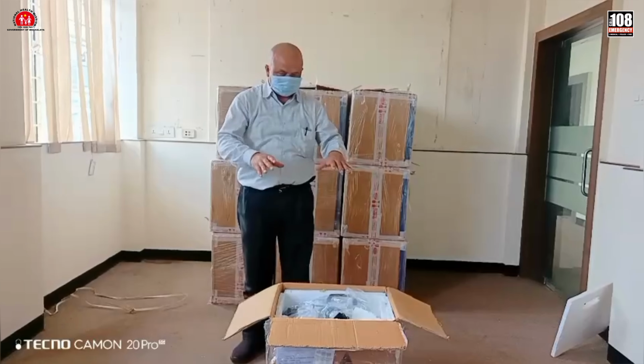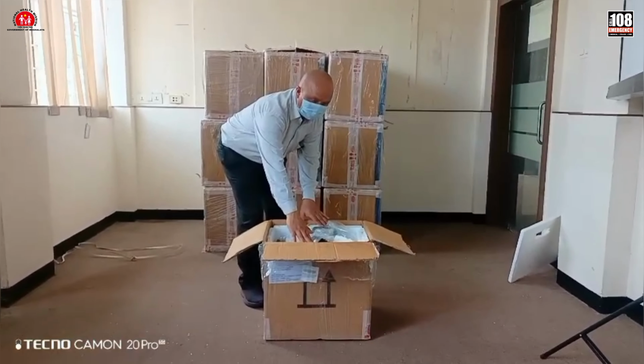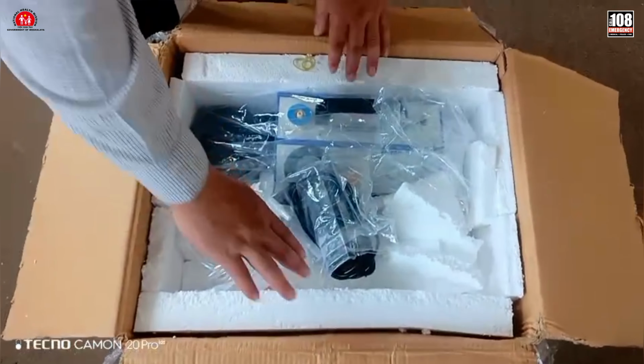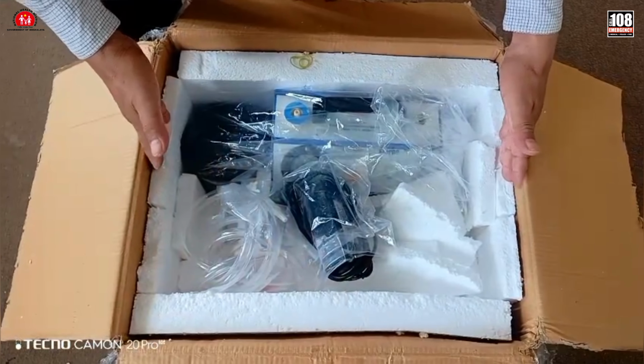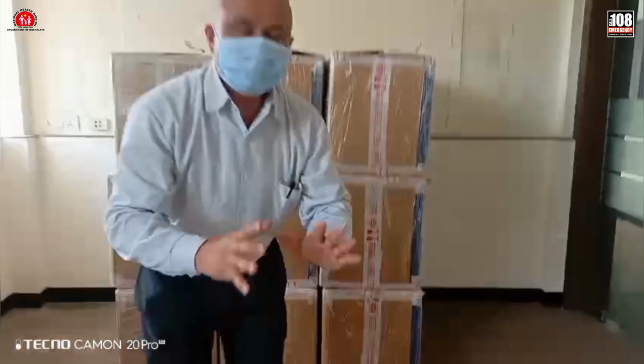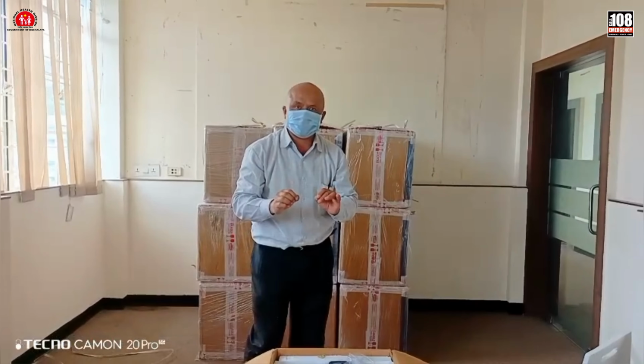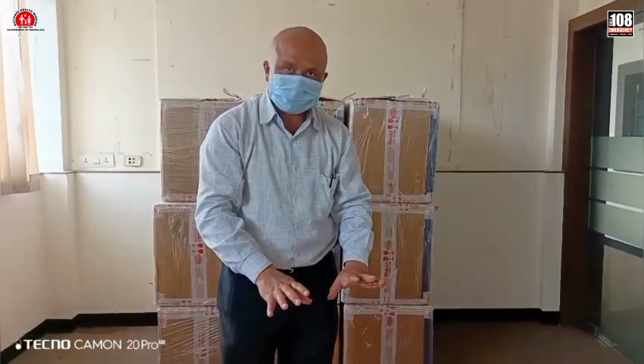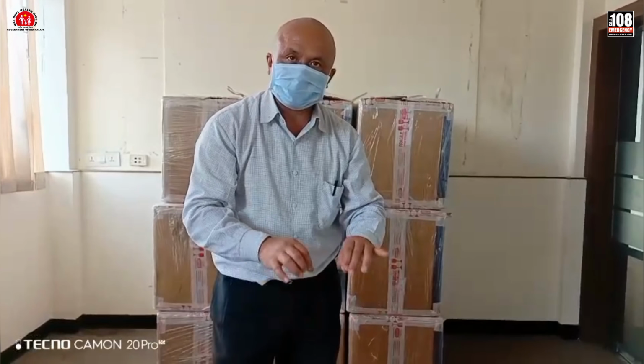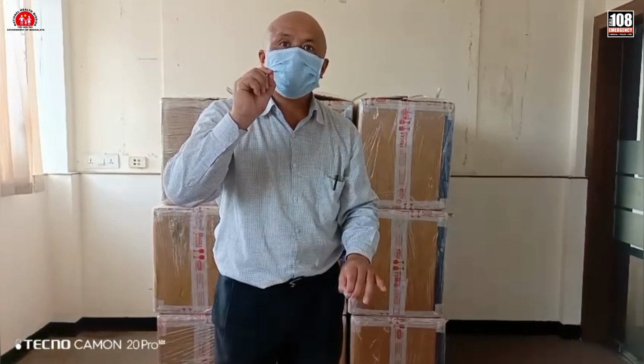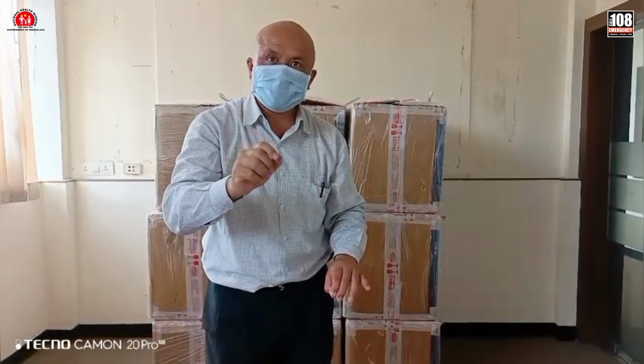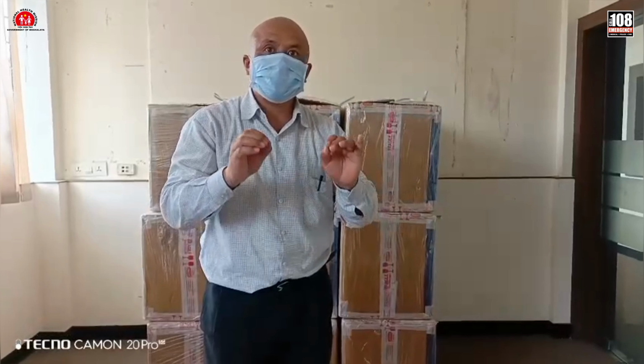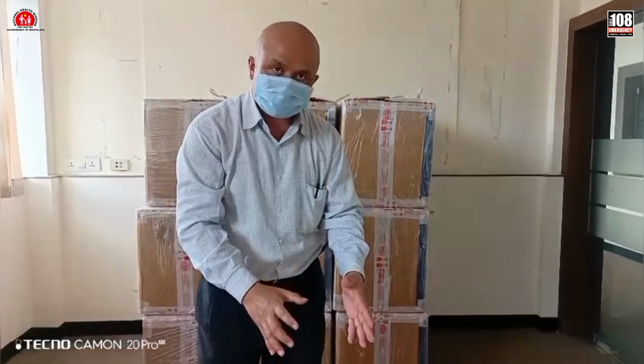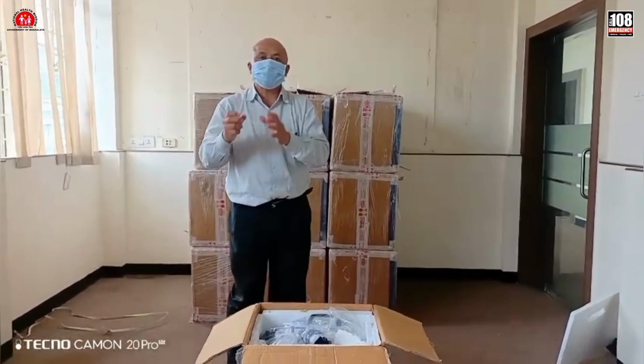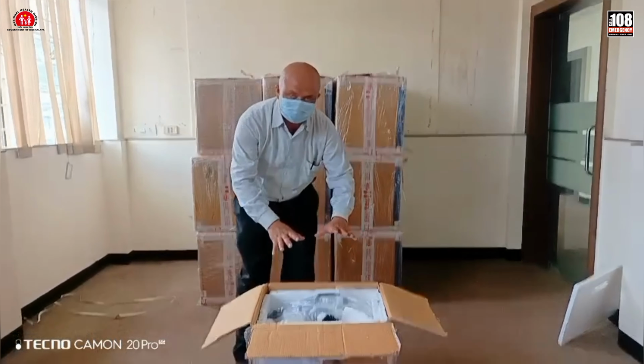And please remember, if you just have a look here in this container, the suction machine is being provided in this way with the thermocols at the side of the suction machine. Please remember, my friends, this is very important. If you just keep the suction machine outside this box in your ambulance, the suction machine will be down within a very short time because all the screws will loosen up and then the suction machine will not be able to function properly anymore. So please, when you have removed the suction machine to use it to do suctioning on a patient, please remember to put it back.